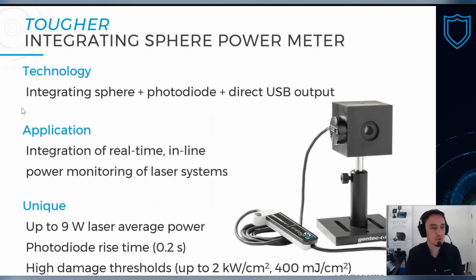So quick overview. Technology for the integrating sphere. You have the integrating sphere coupled with a photodiode with a direct USB output. This is really good for integration of real-time inline power monitoring of laser systems, because that goes up to 9 watts of laser average power, with the benefit of the fast rise time of the photodiode, typically 200 milliseconds. So you can switch from laser to laser really fast and run your measurement quickly, with a high damage threshold as well. It's 2 kilowatt per square centimeter in laser power density.